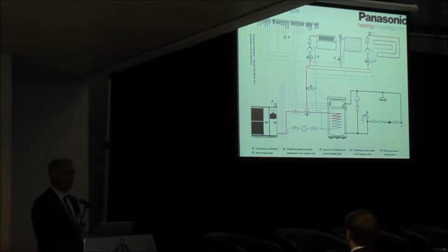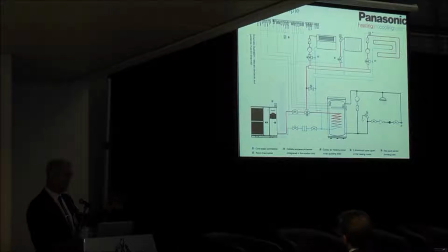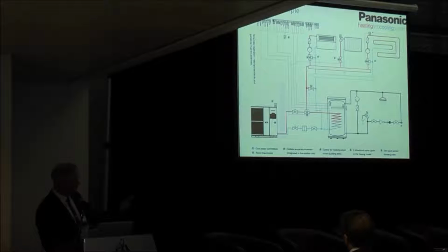You can connect the heat pump unit to a standard domestic time clock, a very simple control system that the end user can use, so that you don't want him interfering with the heat pump controller. But again, if a guy is technically savvy, there's no problem at all for him to interfere with the heat pump controller. Nothing you do to the heat pump controller will damage the heat pump, unless you hit it with a hammer, of course, but nothing you do by pressing buttons will damage the heat pump.